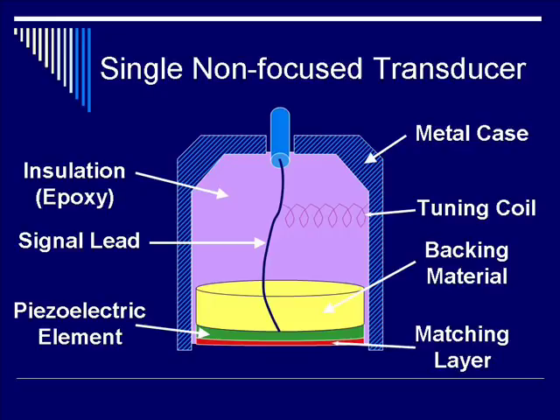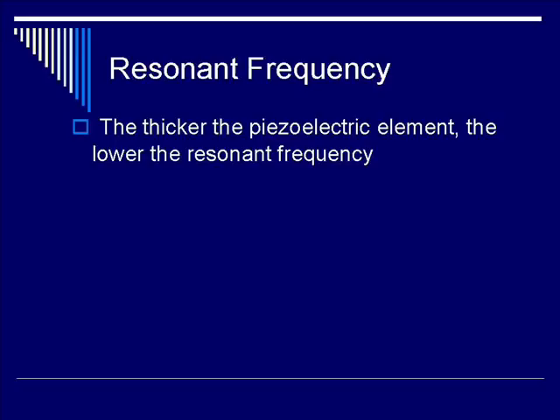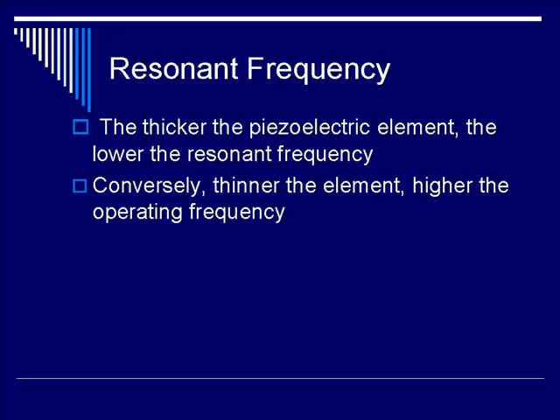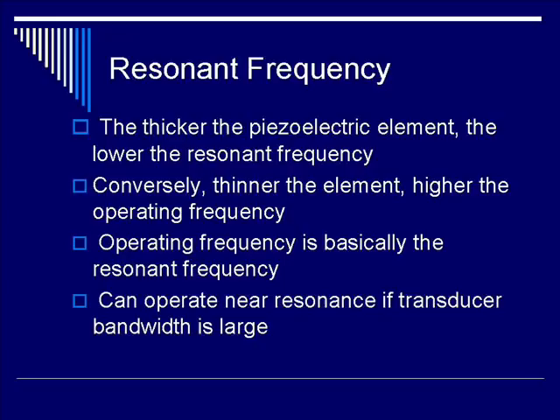What is the resonant frequency? The resonant frequency depends on the thickness of the piezoelectric element: the thicker the element, the lower the resonant frequency; conversely, the thinner the element, the higher the operating frequency. So for high-frequency operation, you want to use as thin an element as possible. The operating frequency is basically the resonant frequency of the material; however, if the material has high bandwidth, you could operate near the resonant frequency and use a wider range of frequencies.